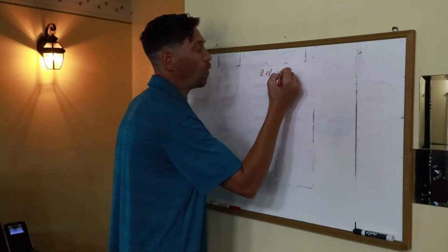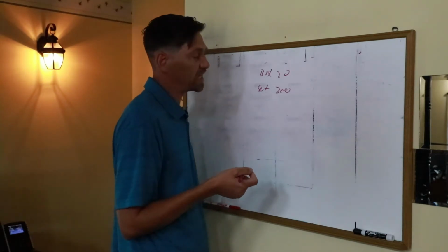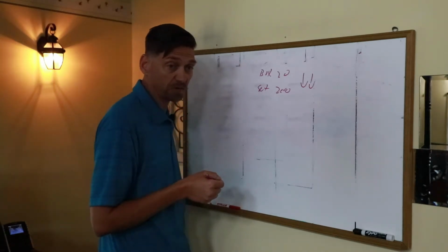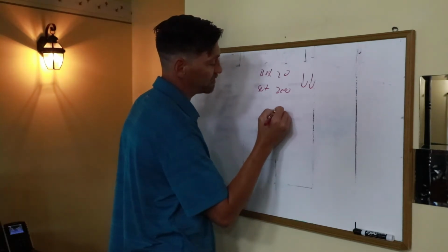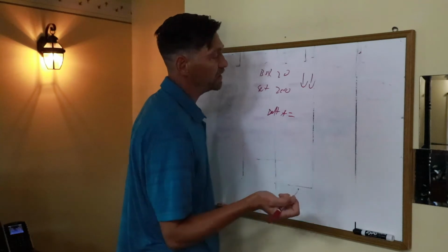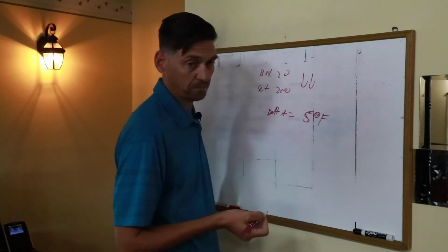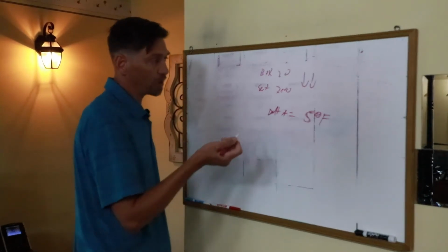The concern would be if you had a box temp of 20 and you had it set to 0 and it's high speed, so the engine's on high speed and the fan's running high speed and it's supposed to be cooling, obviously, right? And you're like, it's not doing it, it's not doing it. And you went into those settings and you saw the delta T was only 5 degrees. Then we're out of Freon. There was a leak, something's broke, and it's not cooling like it should be.